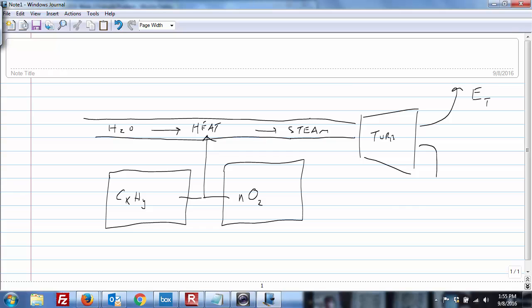But if you recover that steam, you've essentially recaptured that thermal energy. So if this happens, really all you're getting is the lower heating value of the fuel. So remember, I'll just write it as energy sub C for chemical. Chemical energy is here, turns into thermal energy. If that thermal energy leaves as steam off to the atmosphere, you've captured the so-called lower heating value. If you bring it back into your system, what you're looking at is the higher heating value.